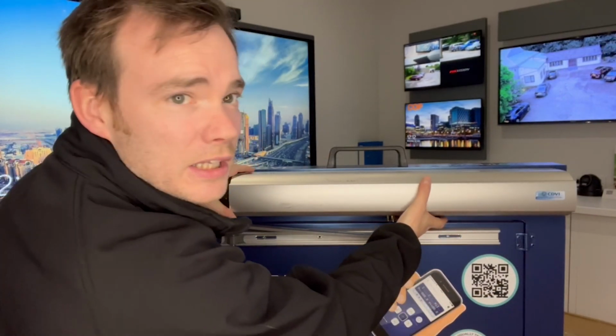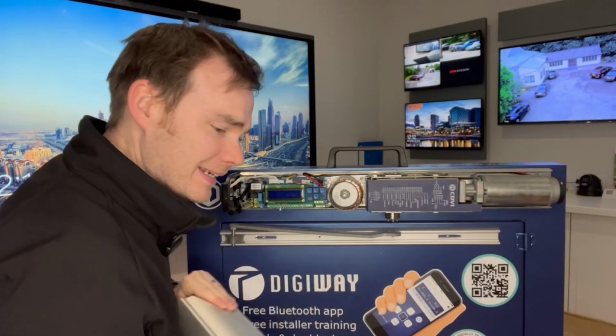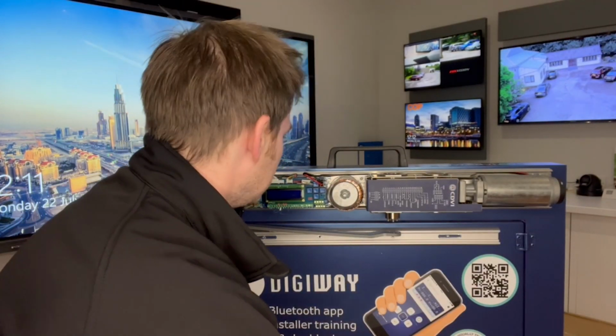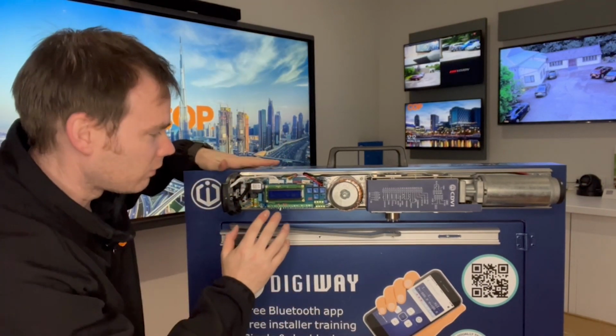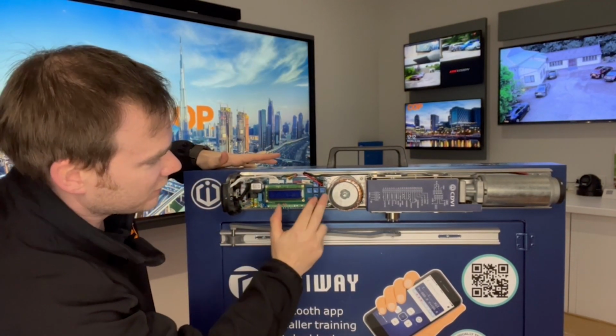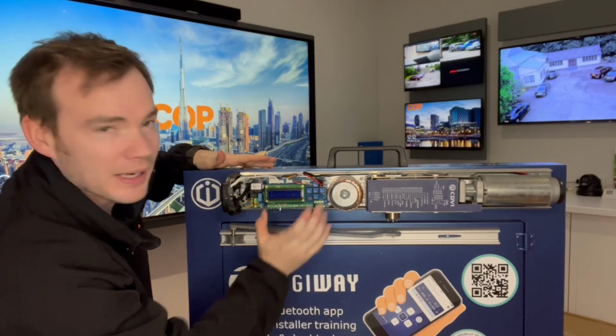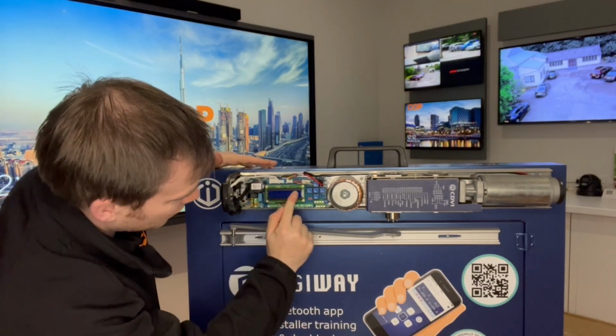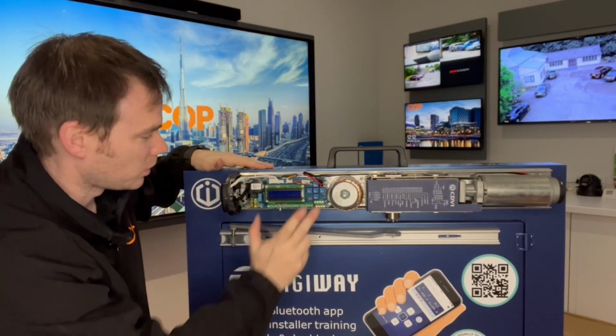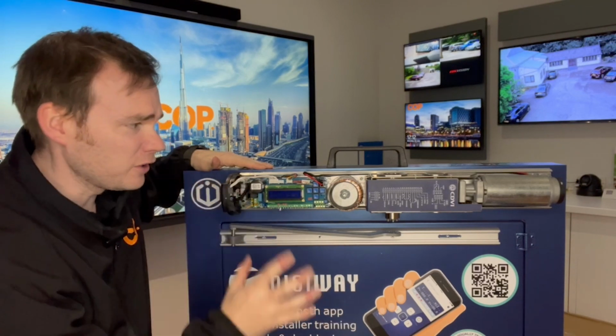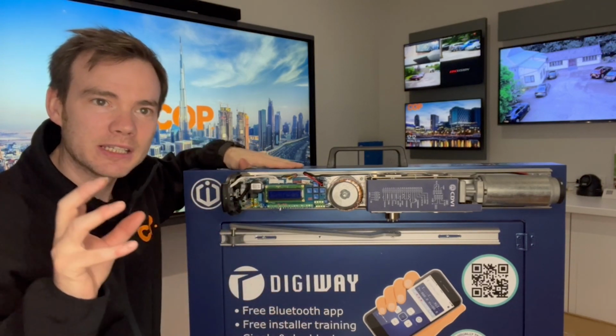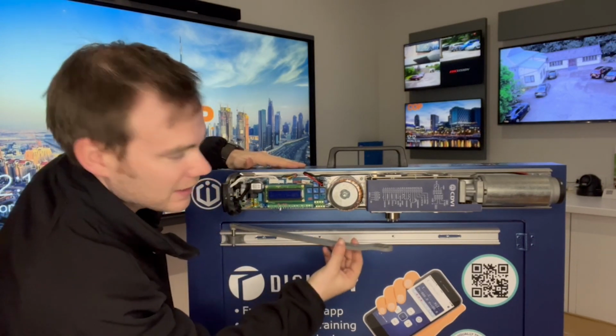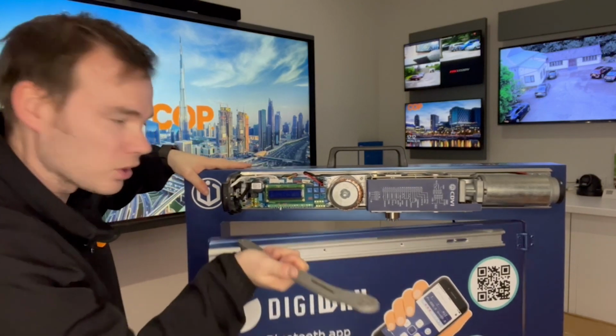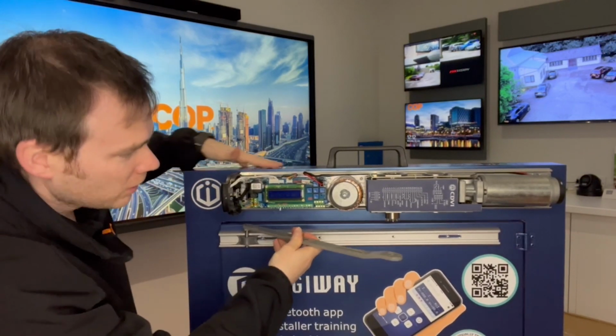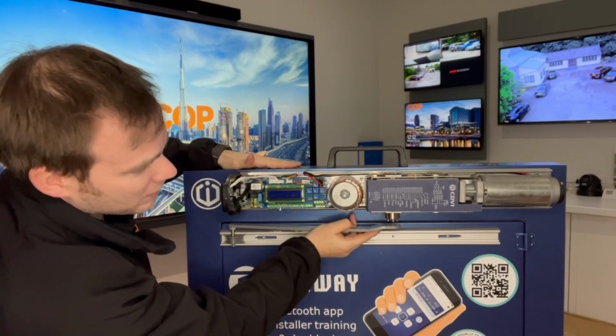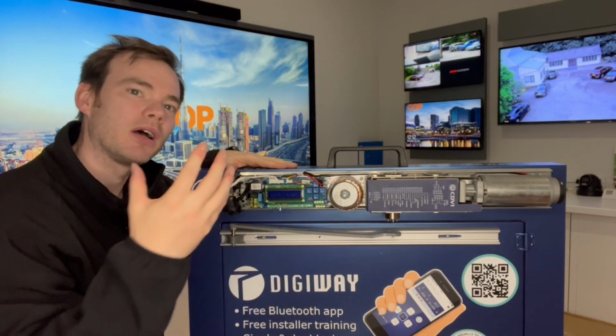So what we're going to do is just take this front cover off, and then we can see the inside of this Digiway. All our control settings are done from these 5 keys here: left, right, up and down, and the center one is our OK button. We also have an LCD readout, which tells us what setting we're going into. The first part, as I mentioned, is the spring pre-tensioner, which is basically where we set the tension limit for the door. So this is the door that's going to be opening here, as we can see, and that's freely open there. We need to hook that onto there, but set the spring tension so it knows at what limit to shut the door.